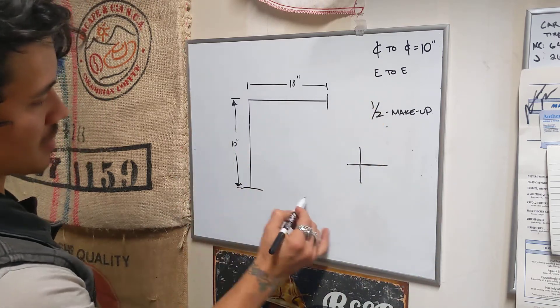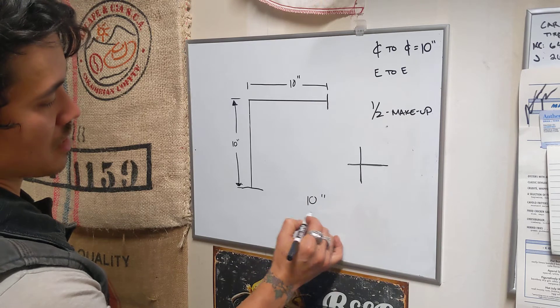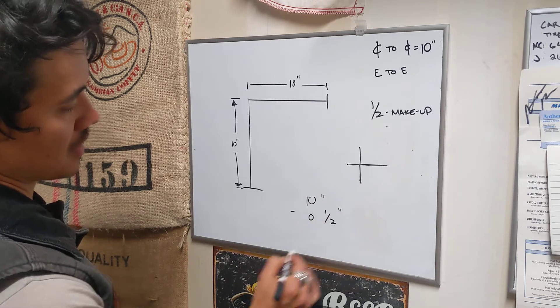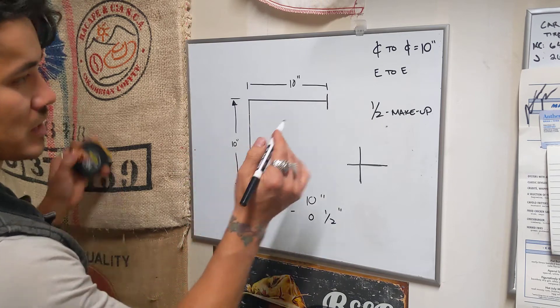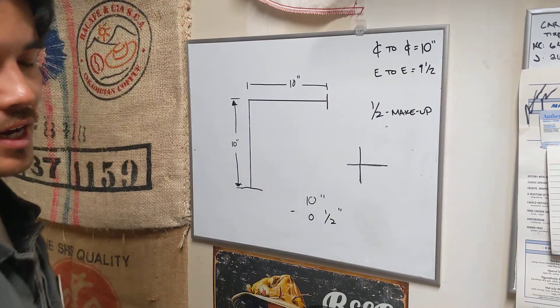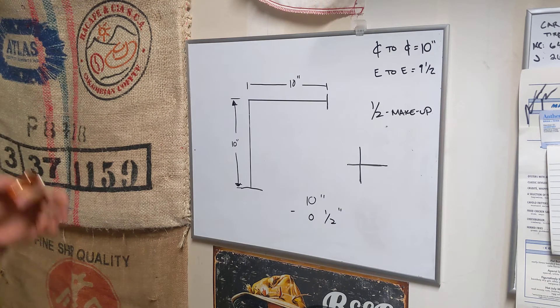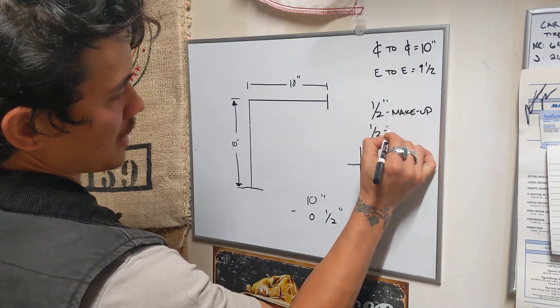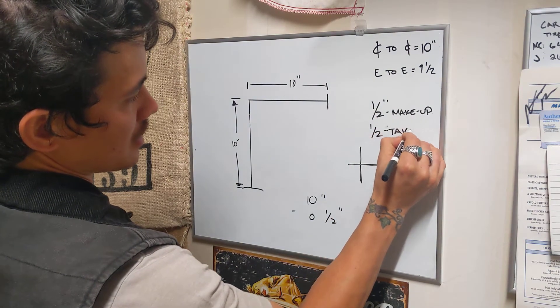The actual makeup is going to be we'll call it half an inch just to make it easy. So you have center to center, you're going to take 10 inches but you're going to subtract half an inch. So that's going to leave you with an end to end cut of nine and a half inches. That can be really confusing at the beginning. So we have a half an inch makeup and a half inch takeoff.